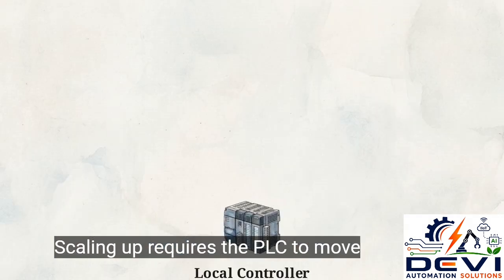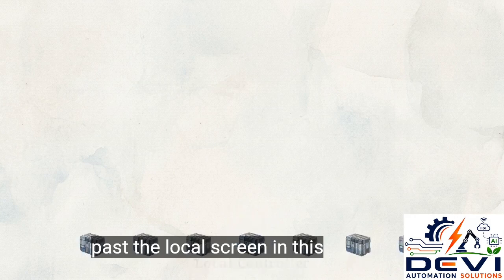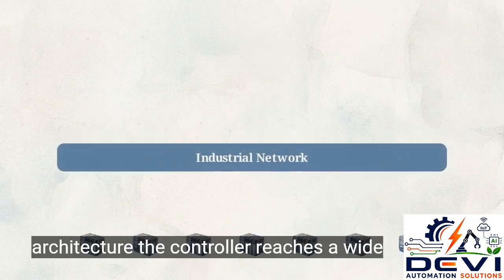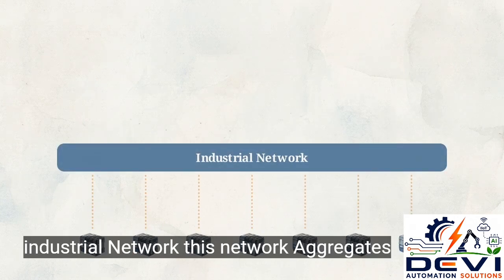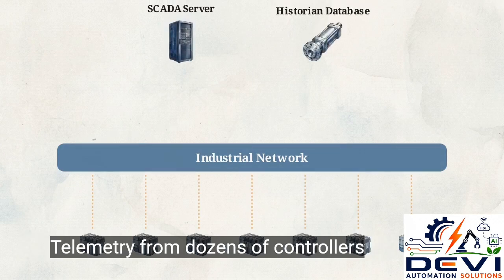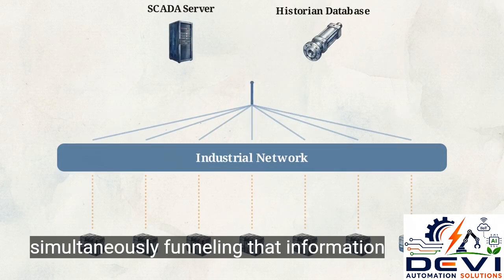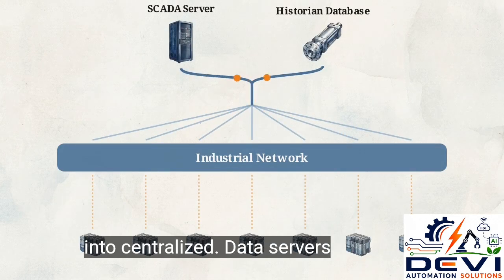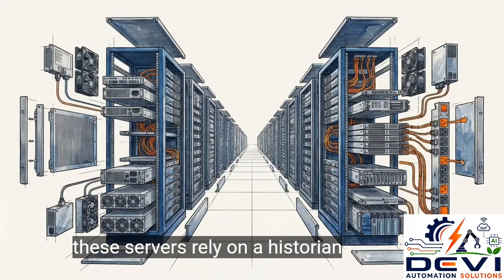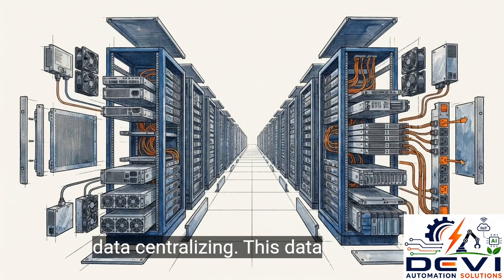Scaling up requires the PLC to move past the local screen. In this architecture, the controller reaches a wide industrial network. This network aggregates telemetry from dozens of controllers simultaneously, funneling that information into centralized SCADA servers. These servers rely on a historian database, a high-capacity software repository that logs and indexes years of plant-wide performance data.